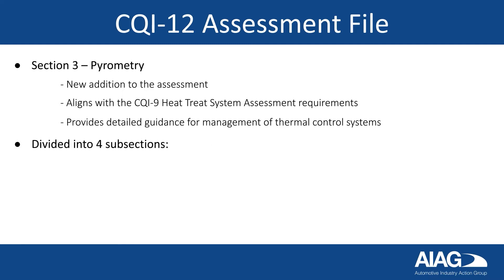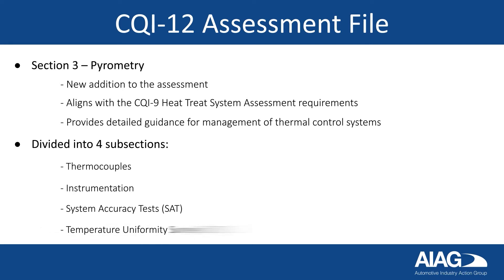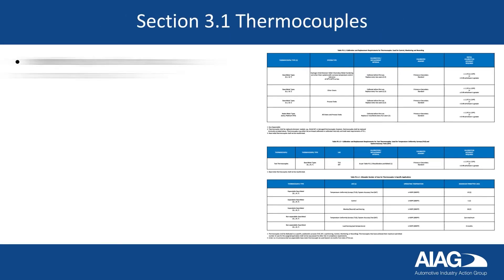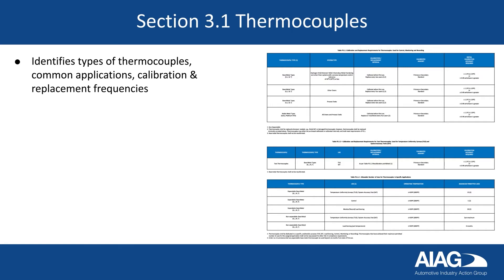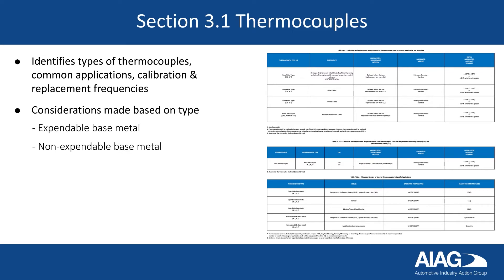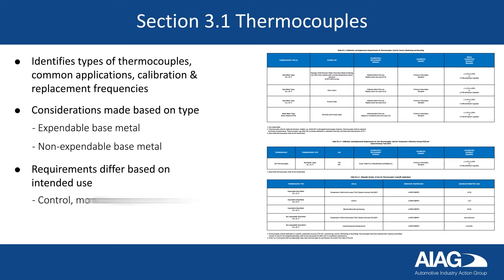It is divided into four subsections: thermocouples, instrumentation, system accuracy tests, and temperature uniformity surveys. Section 3.1 identifies types of thermocouples, common applications, calibration frequencies, and replacement frequencies. Considerations are made based on the type of thermocouple, which can be expendable or non-expendable base metals. Requirements differ based on the intended use so that more critical operations are more tightly controlled.